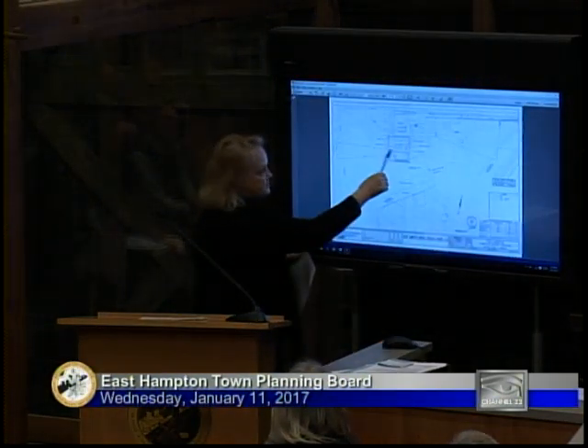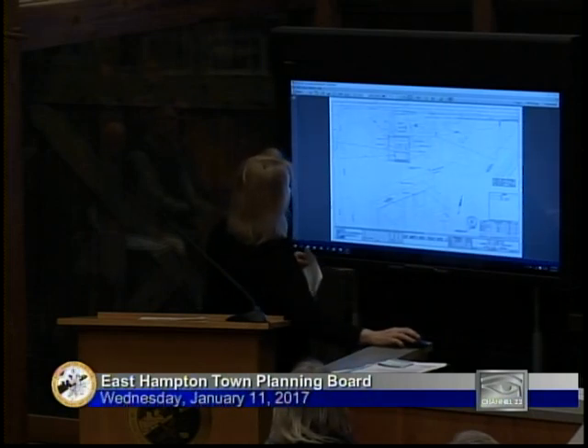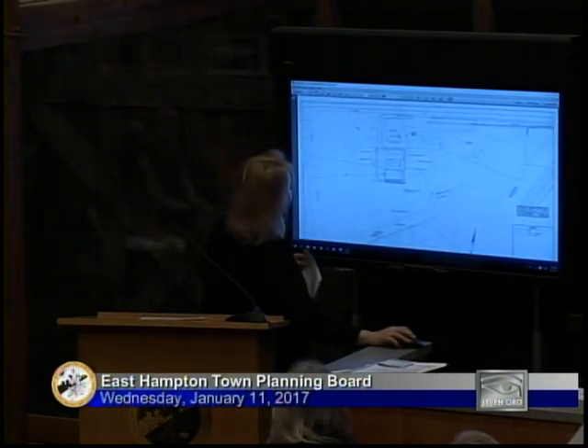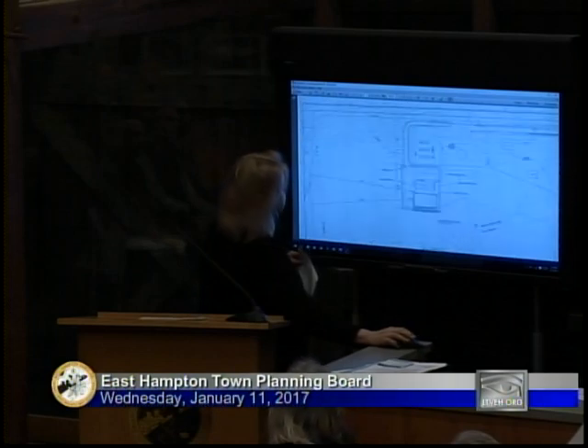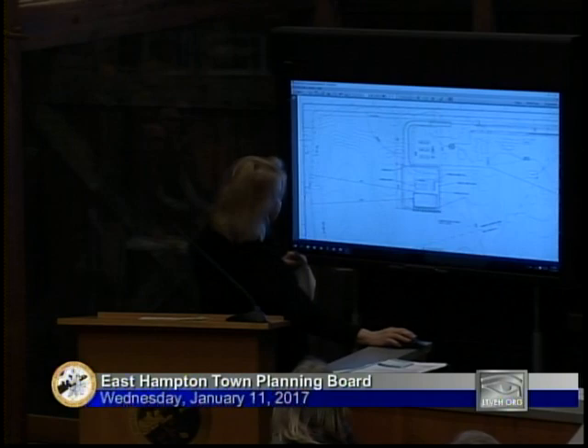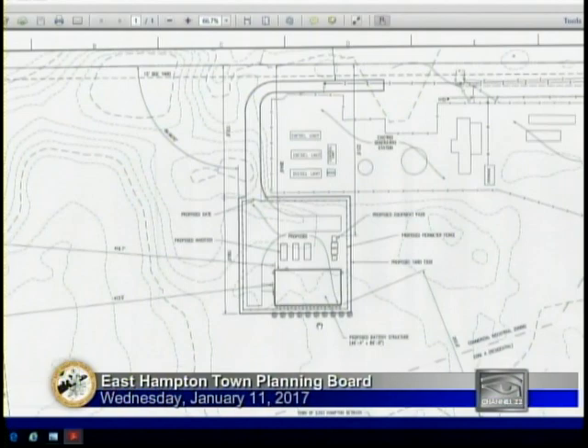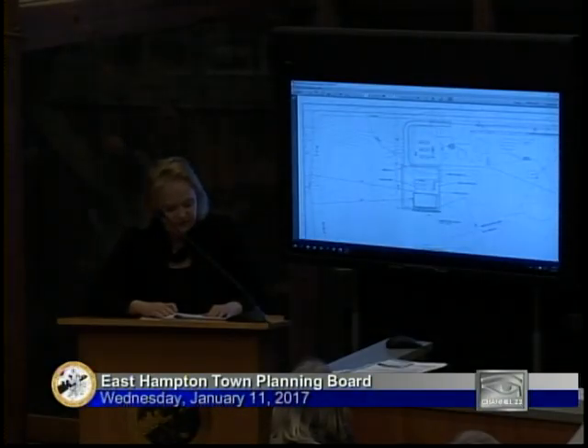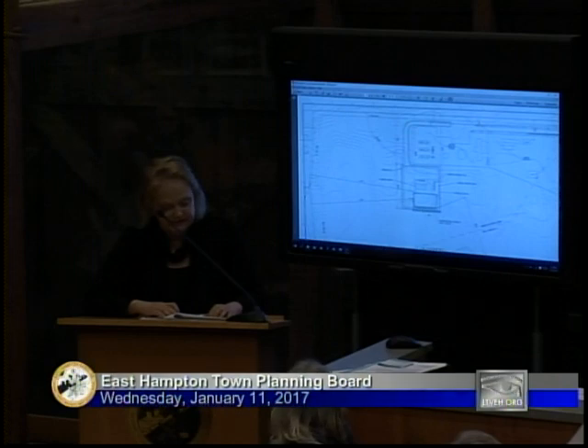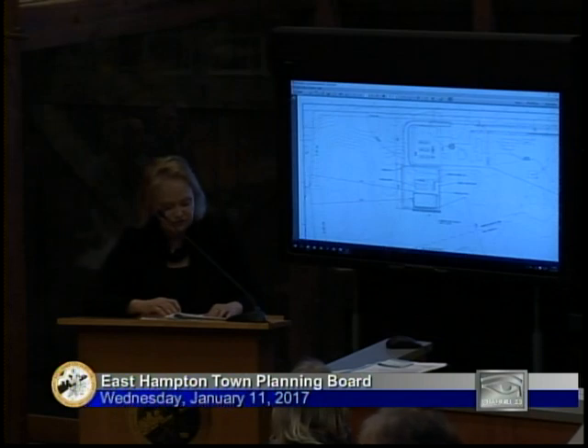This square represents the proposal, and so you have the building with the battery storage in here. There are 3 inverters on these pads, and then there's a series of equipment pads to the side that are part of the project. So the inverters convert the alternating current (AC) energy from the power grid to direct current (DC). The DC energy then goes into the batteries that are housed within the energy storage structure.